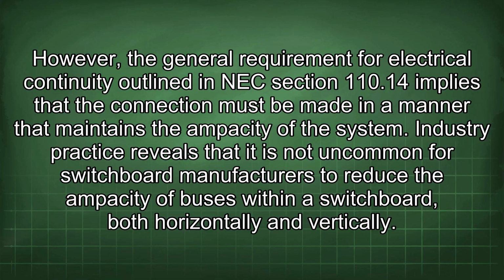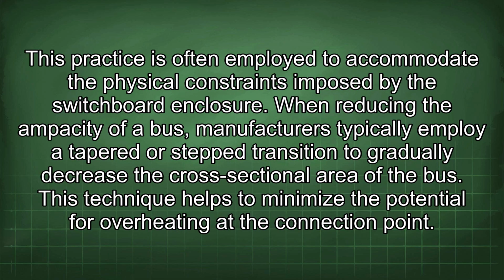Industry practice reveals that it is not uncommon for switchboard manufacturers to reduce the ampacity of buses within a switchboard, both horizontally and vertically. This practice is often employed to accommodate the physical constraints imposed by the switchboard enclosure. When reducing the ampacity of a bus, manufacturers typically employ a tapered or step transition to gradually decrease the cross-sectional area of the bus. This technique helps to minimize the potential for overheating at the connection point.